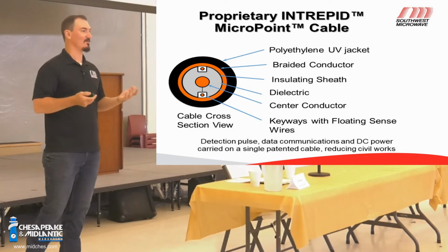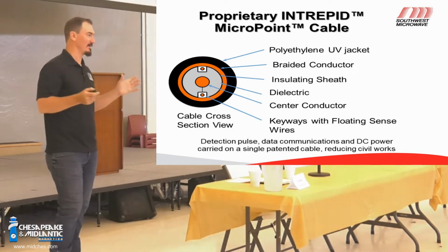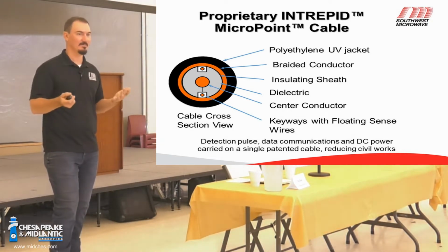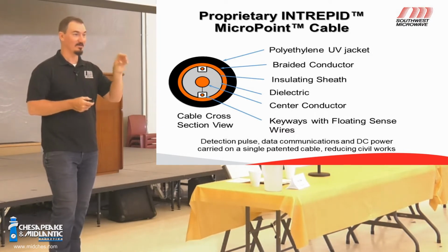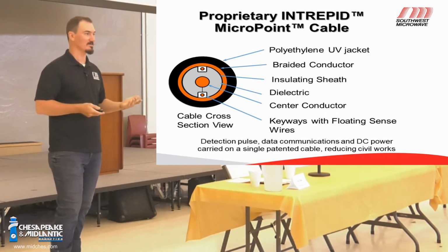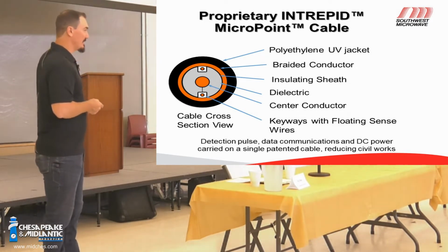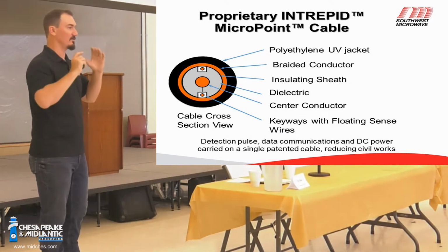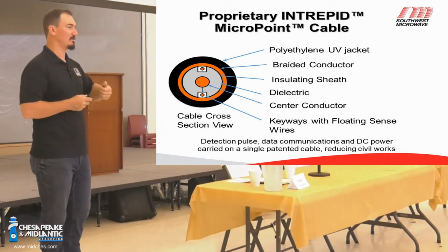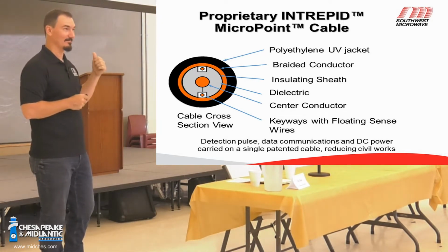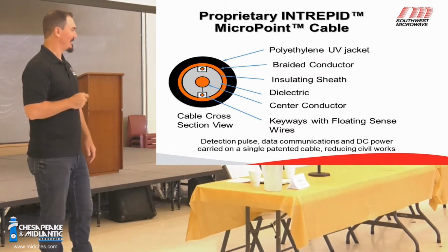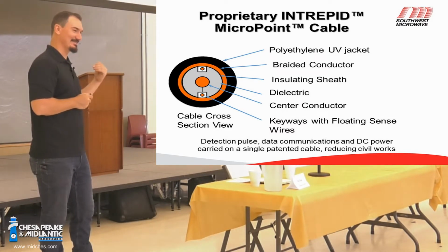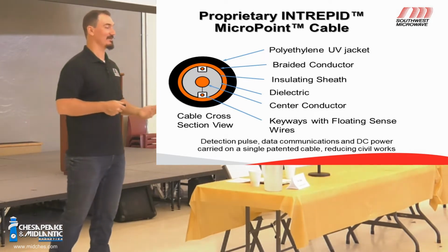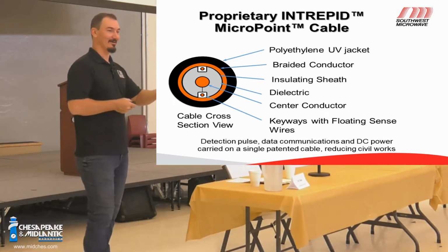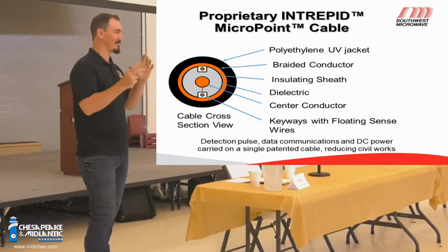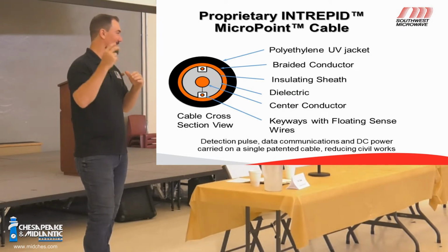Now we use time domain reflectometry, TDR, very fancy words, right? But I call it radar, TDR, same thing. We send information in pulses. Those pulses are reflected back, similar to a radar signal, right? So the only thing that keeps that in is the tinfoil shielding. The tinfoil shielding keeps all electromagnetic interference out and radio frequency interference out. So EMI and RFI are shielded from the sensor, and the radar signal inside is shielded from anything outside.